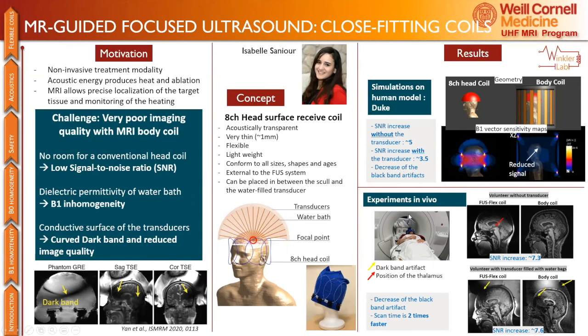and of course no black band artifact. And then in vivo we have some nice images here. This is just the coil, no transducer. The body coil gives a very noisy image, and our coil gives an increase of 7.3. And then with the transducer, so now that's the new coil and also the helmet around it, you get a 7.6 SNR increase. The black band is moved a little bit here.